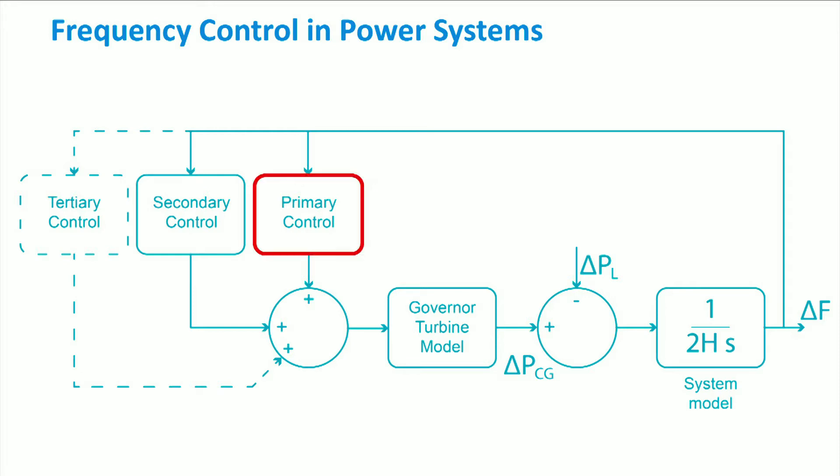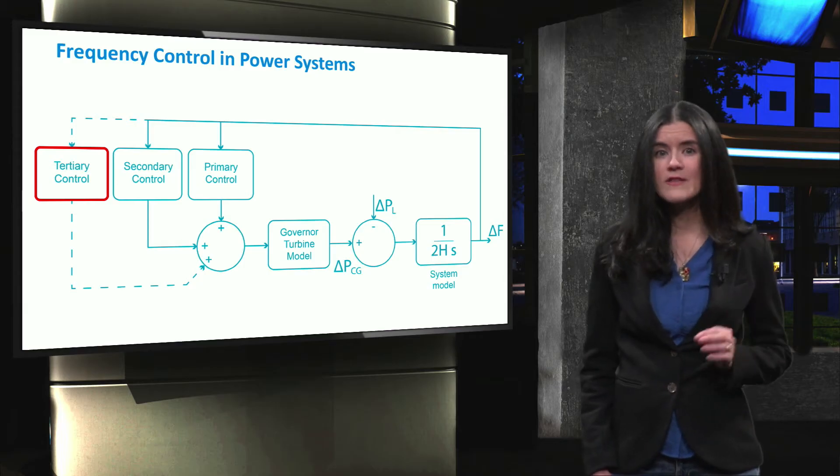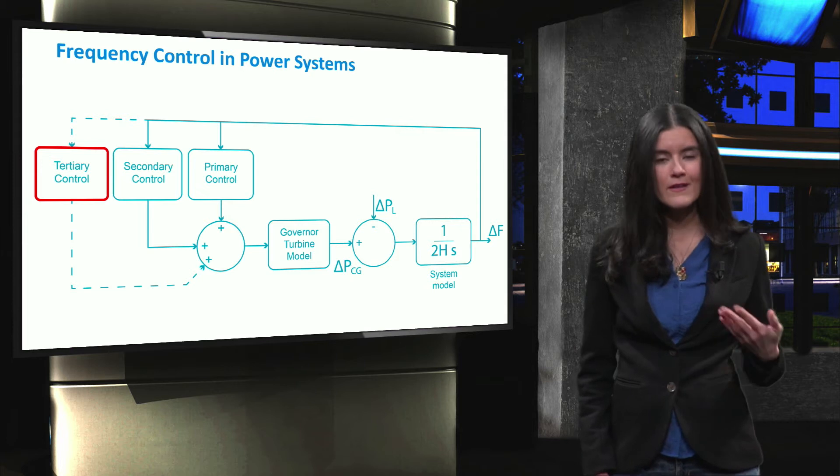In a nutshell, primary control is in charge of keeping the active power balance, secondary control is in charge of restoring the frequency and the power exchange between different areas of the network. Finally, tertiary control is used to restore a sufficient secondary control volume. We will cover each of these control mechanisms in more detail in the coming videos.